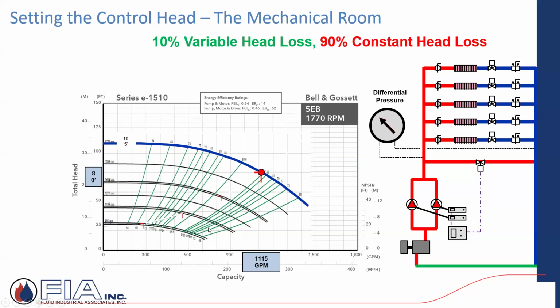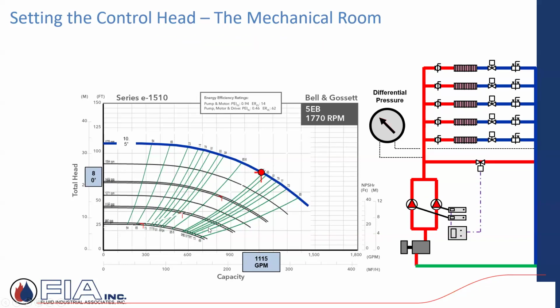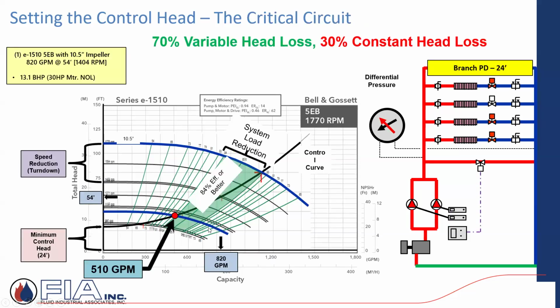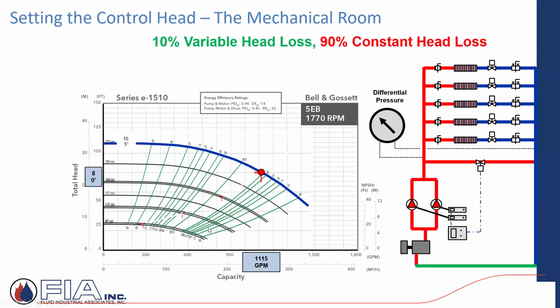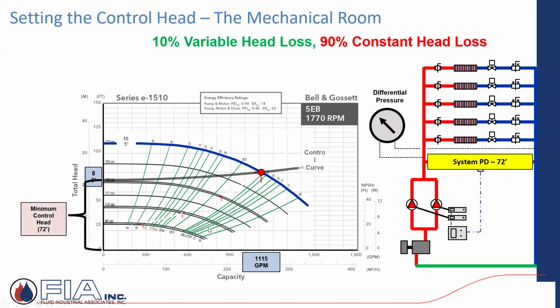Here's an example which says, hey, I am not putting my pressure differential sensors remote out in the building. In this case here, say that furthest terminal unit, but I'm actually doing it in the mechanical room. Look what happens to my variable head loss versus my constant. If that pressure drop is right here in the mechanical room, I've really limited my range of variable loss.